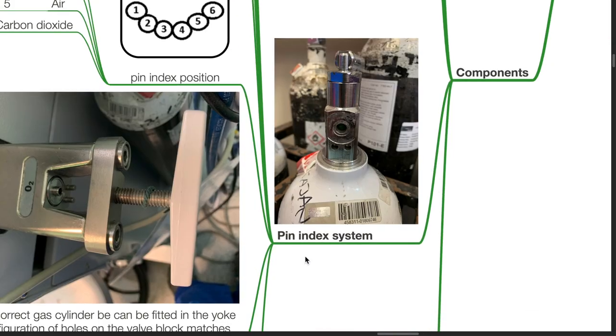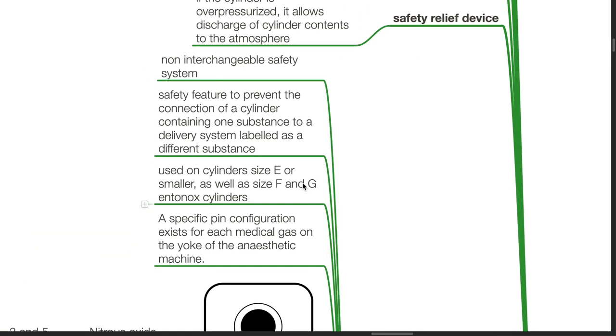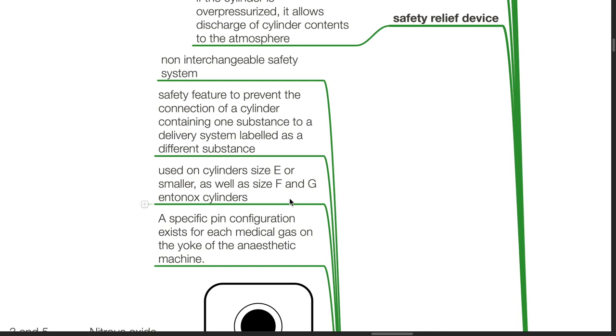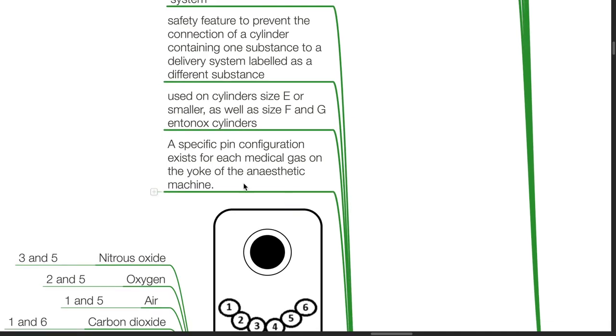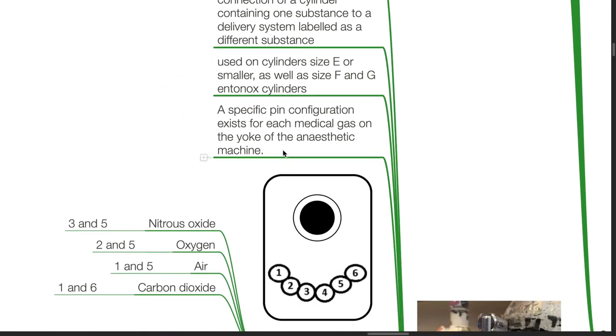Pin index system is a non-interchangeable safety system. It is a safety feature to prevent the connection of a cylinder containing one substance to a delivery system labeled as a different substance. Used on cylinders size E or smaller, as well as size F and G and Entonox cylinders, a specific pin configuration exists for each medical gas on the yoke of the anesthetic machine.